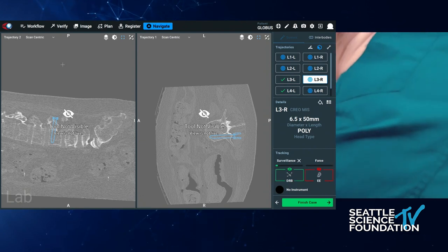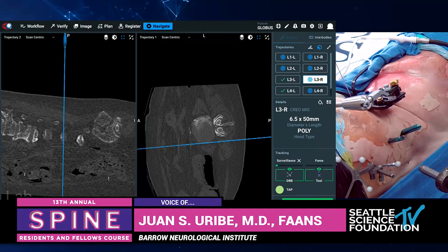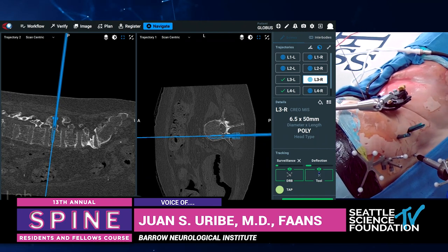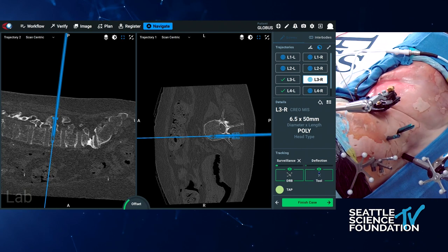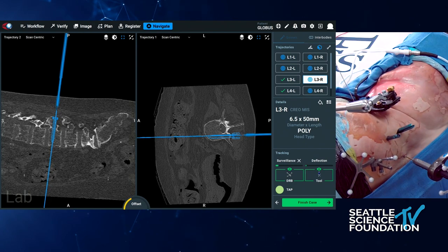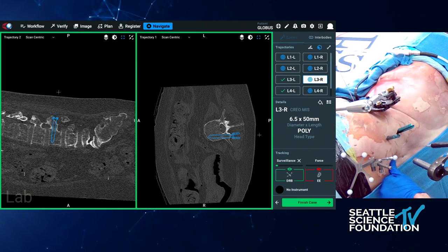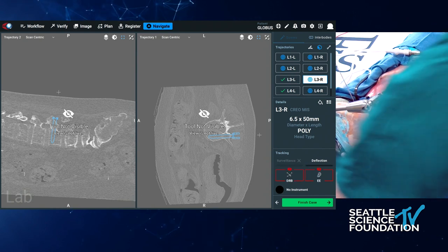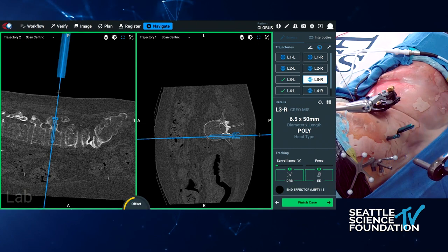He has the option of tapping. To explain the deflection tool and the surveillance marker: you see two little marking tabs above the box that says DRB and Tool. The deflection tool is a gauge of the pressure — as he places pressure on the instrumentation and moves the preoperative navigation scan according to where the end effector is, it's a meter of the pressure applied. If you're doing an open case and your skin incision isn't long enough, the pressure placed on the tool by the skin edges can cause deflection of your driver.